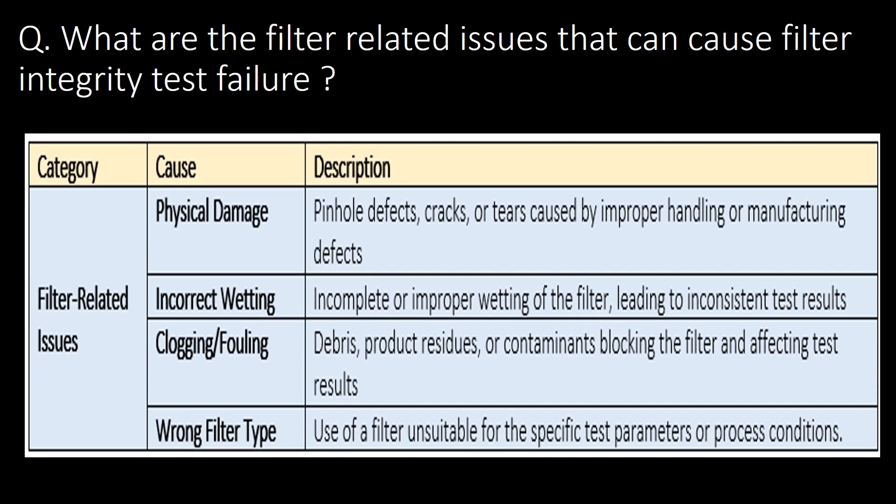What are the filter-related issues that can cause filter integrity test failure? Filter damage, incorrect wetting, clogging or fouling, and wrong filter type are the important filter-related causes that can cause filter integrity test failure. Refer to the table below for more details.